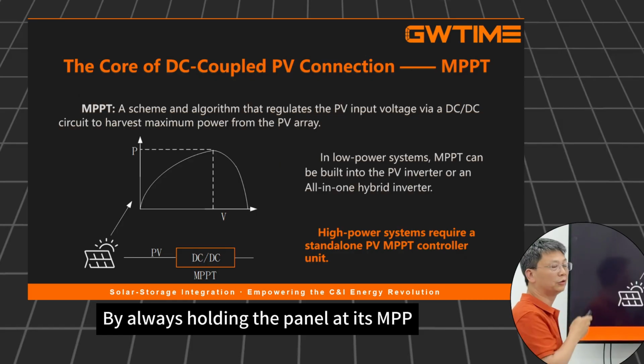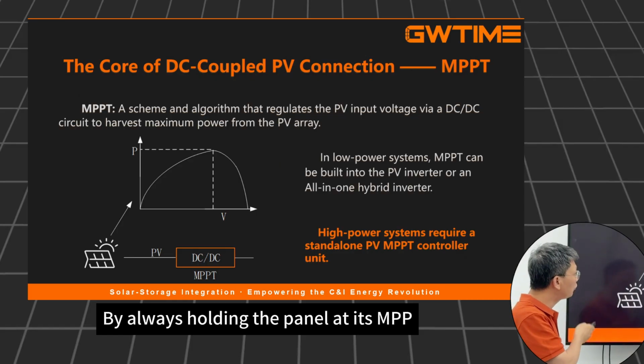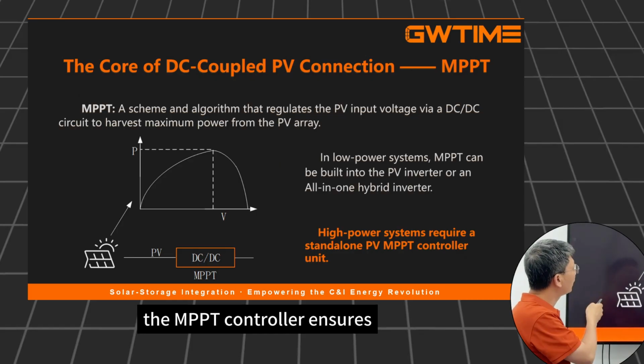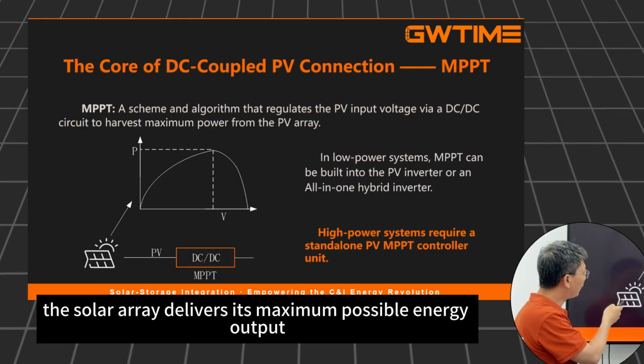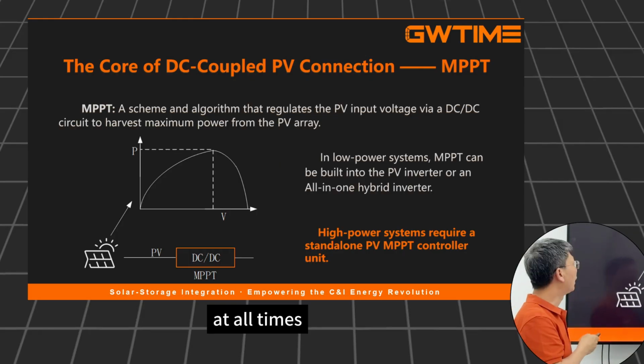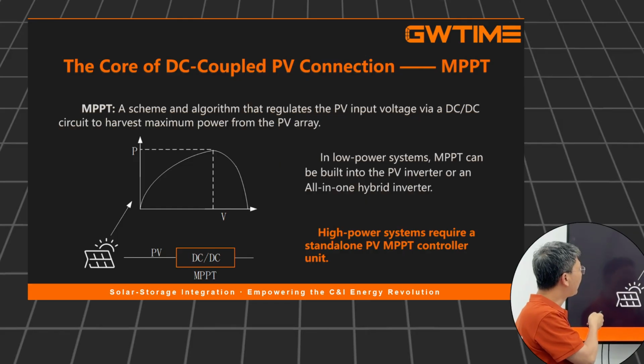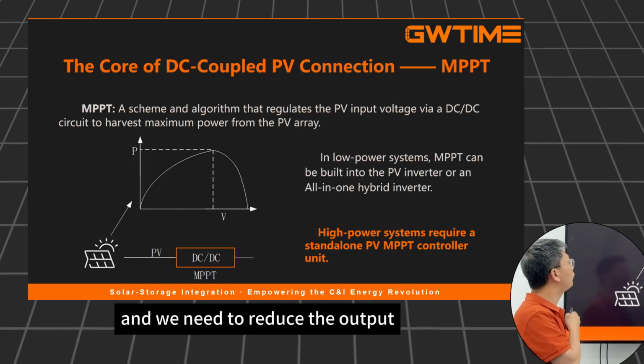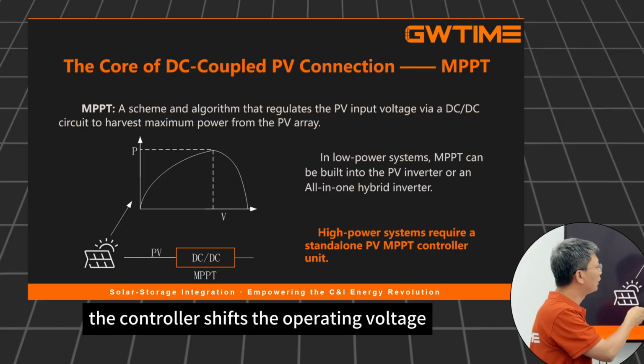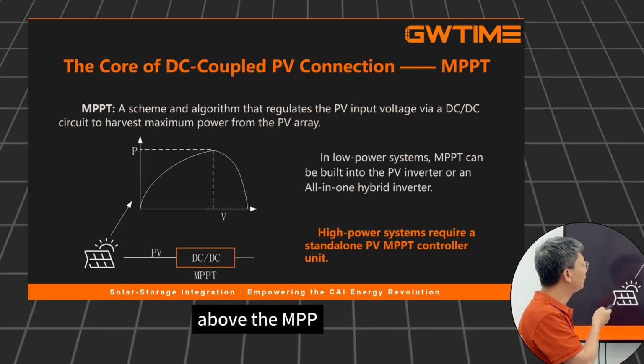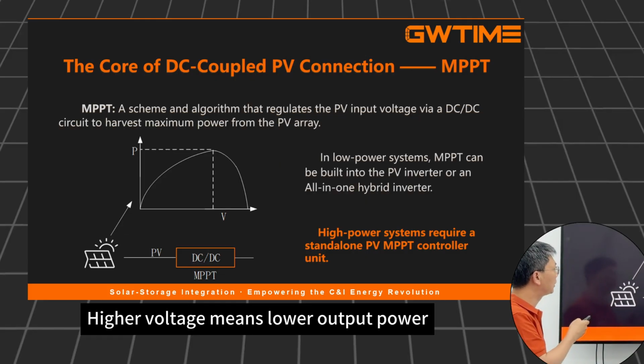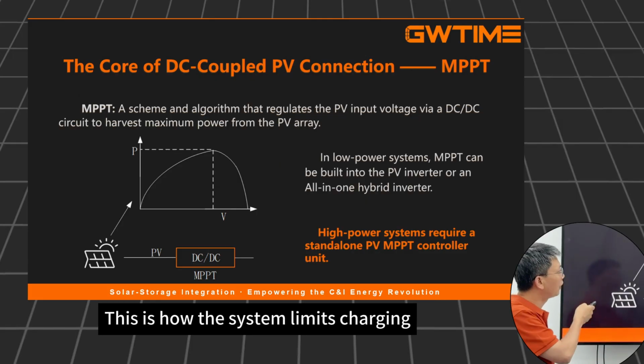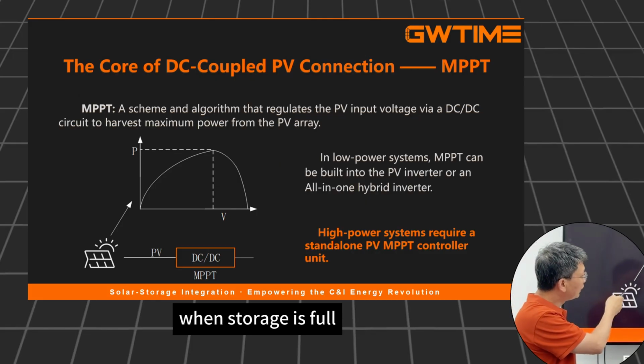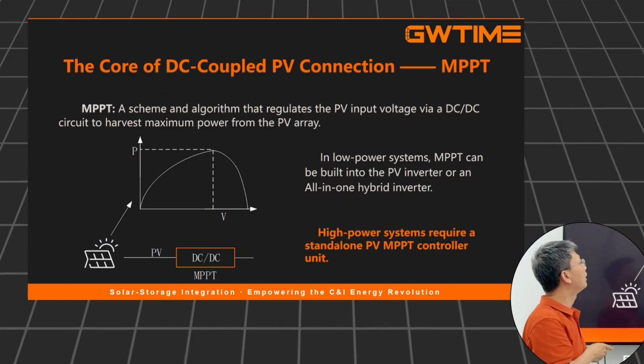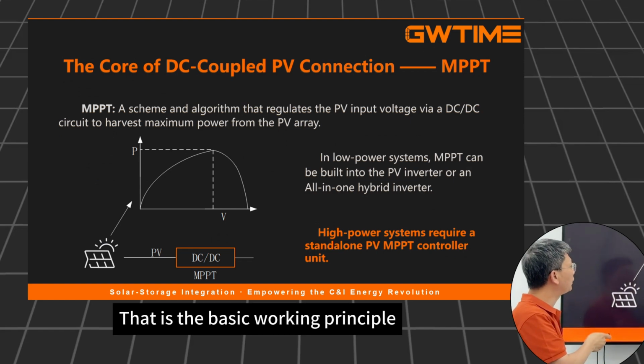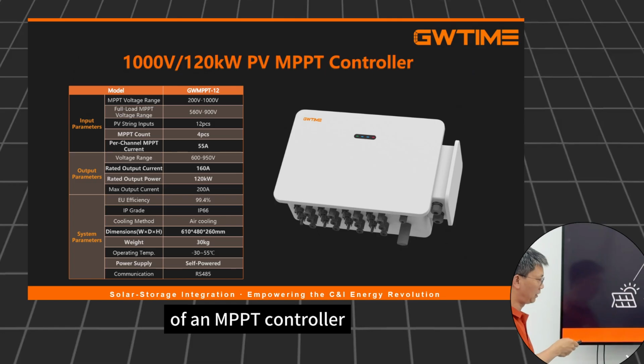By always holding the panel at its MPP, the MPPT controller ensures the solar array delivers its maximum possible energy output at all times. When the battery is full and we need to reduce the output, the controller shifts the operating voltage above the MPP. Higher voltage means lower output power. This is how the system limits charging when storage is full. That is the basic working principle of an MPPT controller.